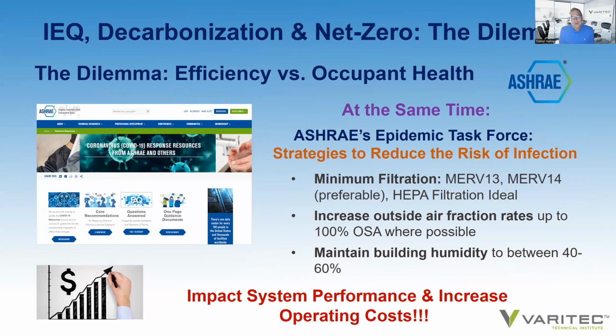But again, in the meantime, we have ASHRAE's Epidemic Task Force saying that to create better IEQ and better indoor air quality and reduce the risk of infection during the pandemic, we need minimum filtration requirements of MERV 13, MERV 14, ideally HEPA filtration, which is not really feasible, but it is optimal. Also, it advises that we increase outside air fraction rates up to 100% outside air where possible. And also to maintain building humidity levels between 40 to 60%. So there's a significant impact on operating costs to employ these strategies to reduce the risk of infection within the built environment.